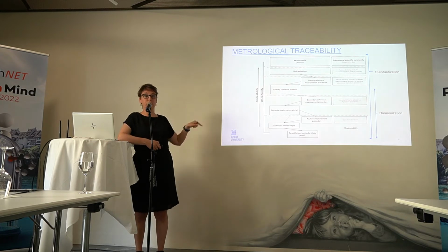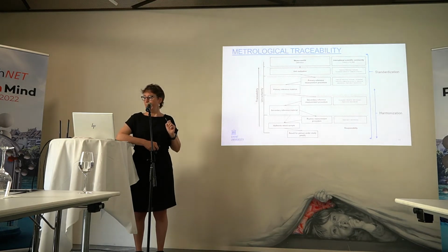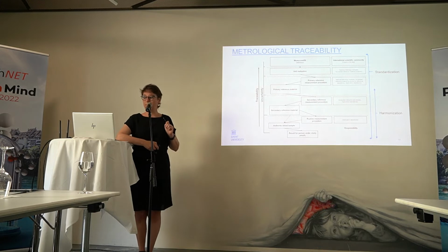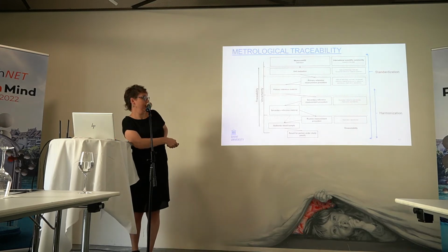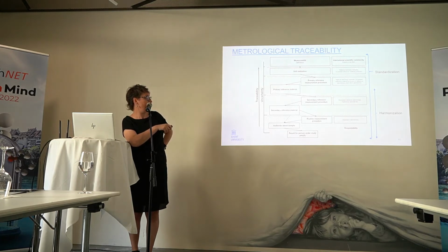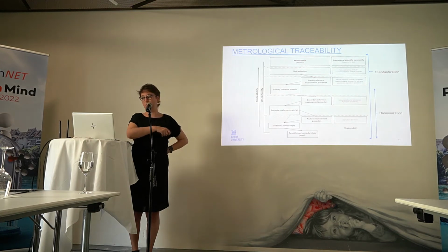So I will guide you through the most important things of this scheme. And actually, just the definition of the metrological traceability chain, it means that the results obtained for a patient sample can be linked to the highest international standards, the definition of the measurement and the SI, via an unbroken chain of calibrators and measurement procedures. So each time this chain should be followed, you can go back to the highest international standards.